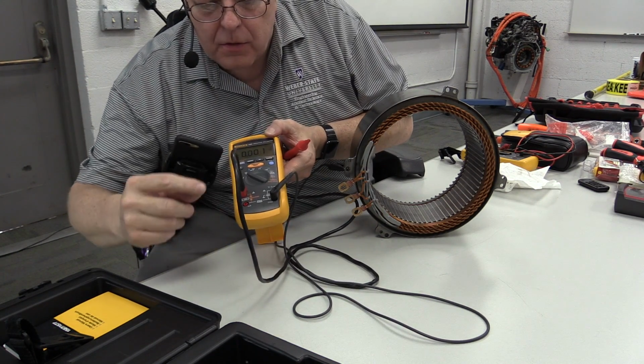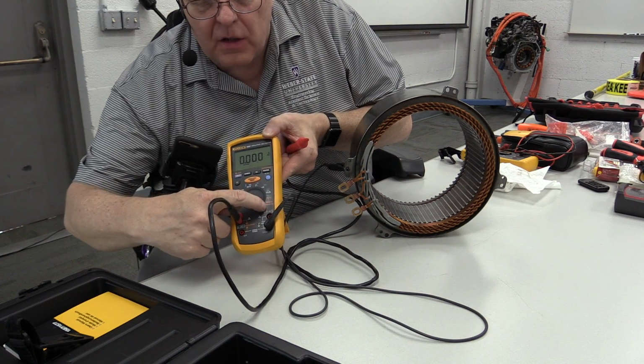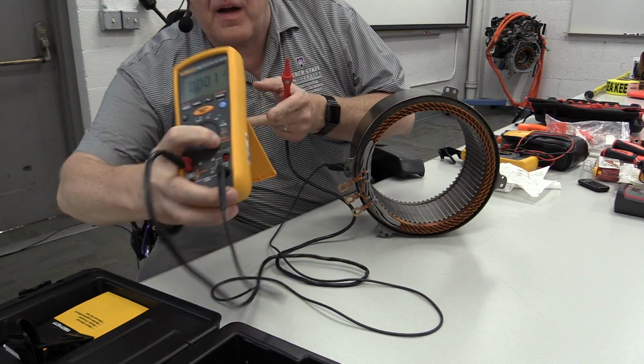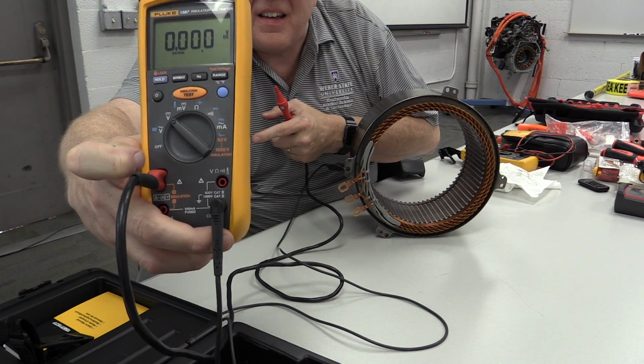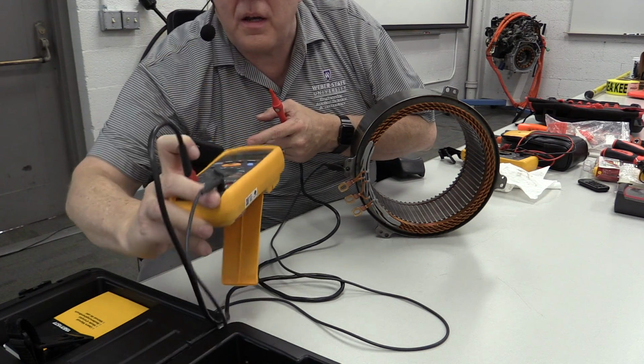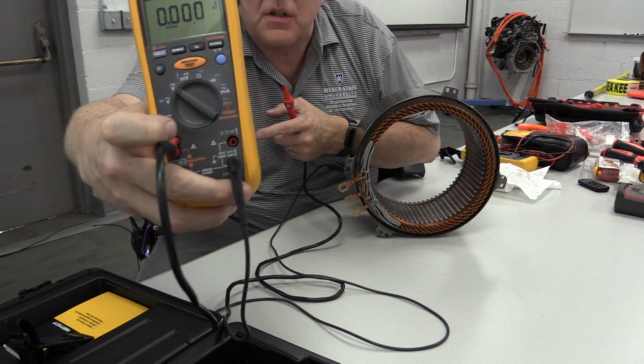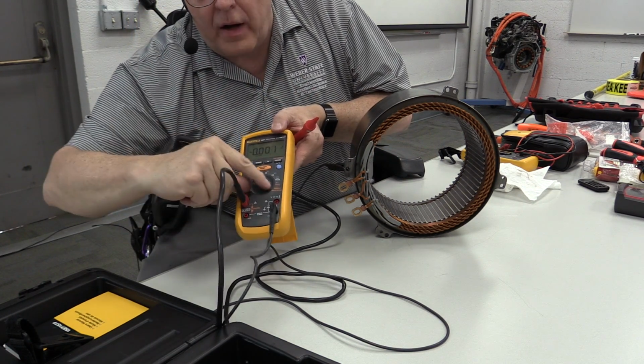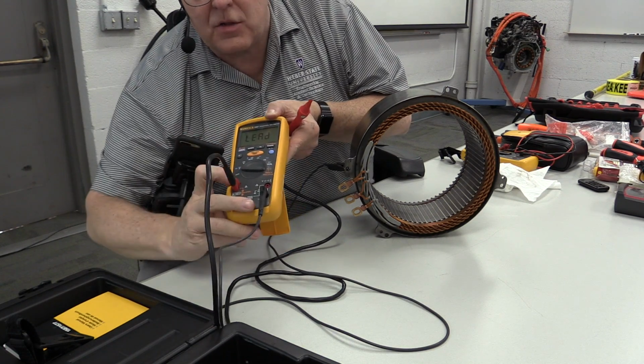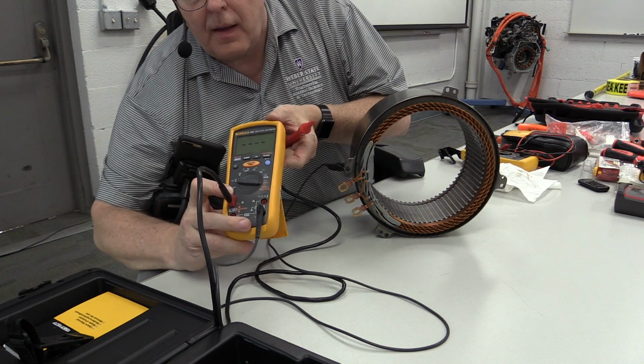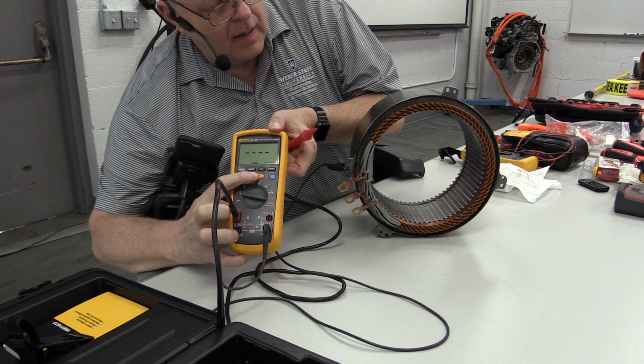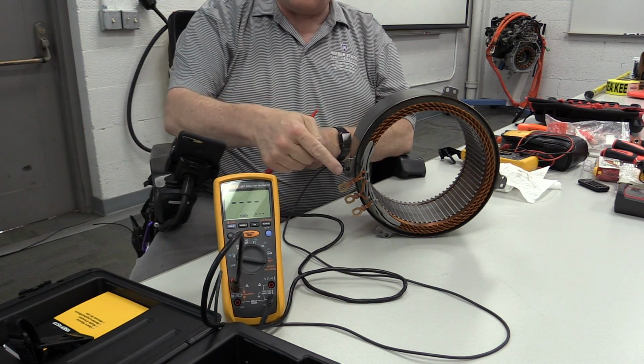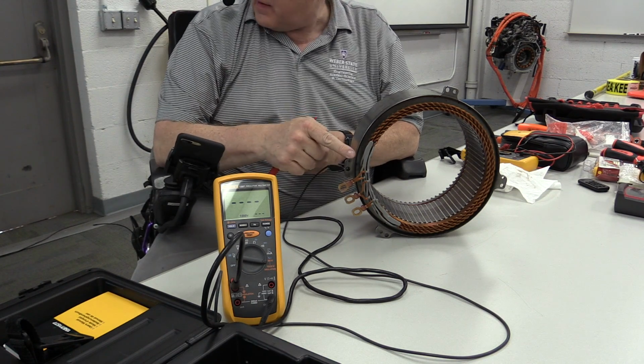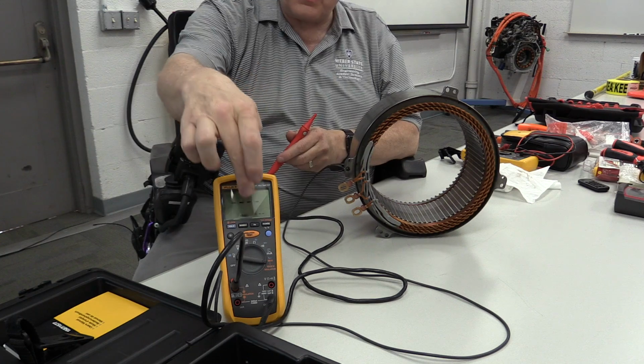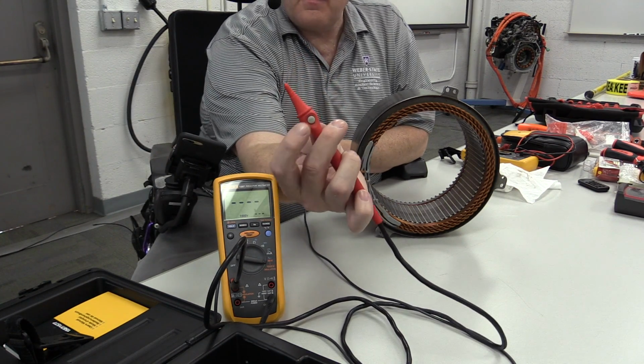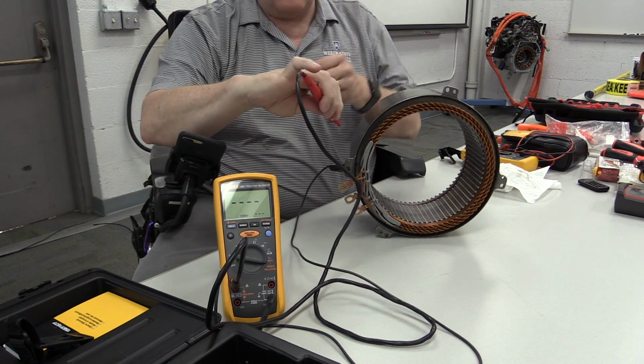one of the leads. Let's flip this to what's called insulation test. So over here on the right hand side, we have orange numbers that read 50 to 1000 volts insulation. So we're not going to put it on ohms. We're going to put it over here to insulation test. And then when we're ready to test the insulation, or test what should be the super high resistance between the stator winding and the housing, we're going to press that orange button, or we can press this button here on the end of the meter lead.